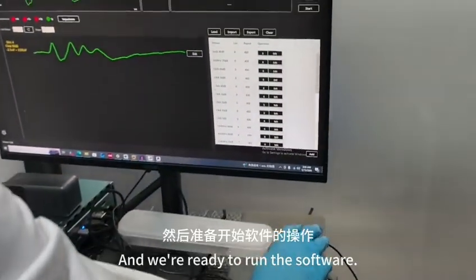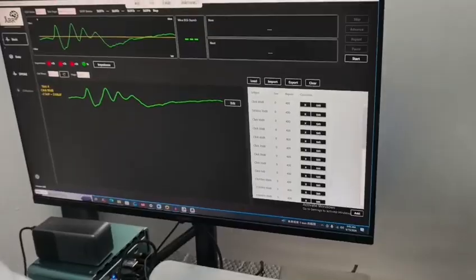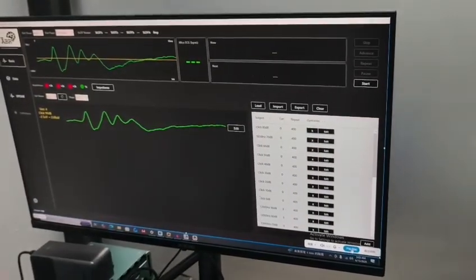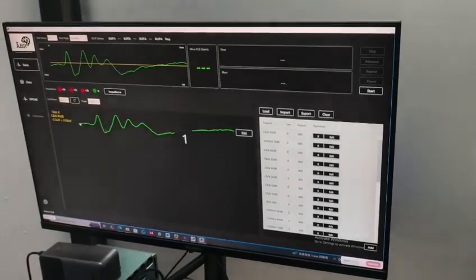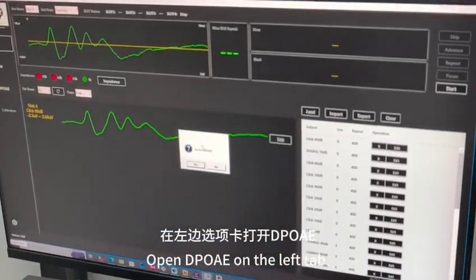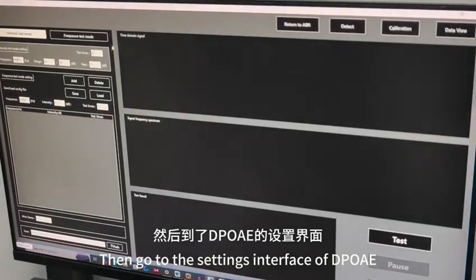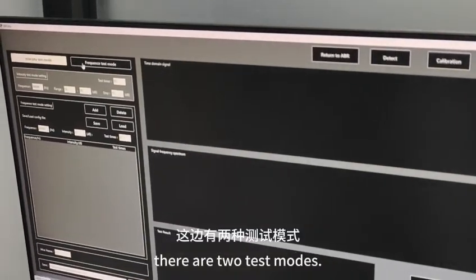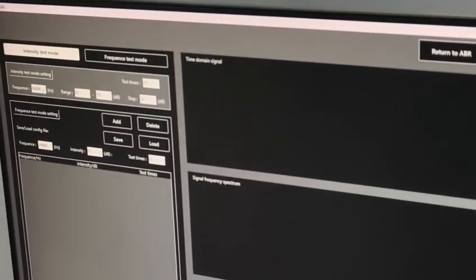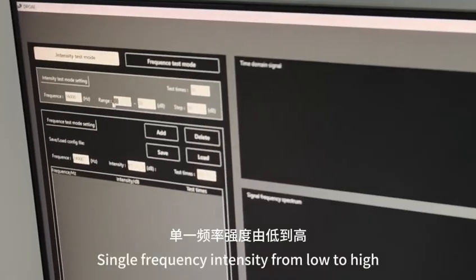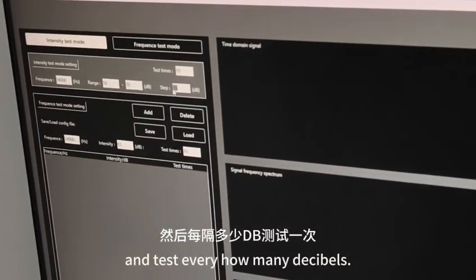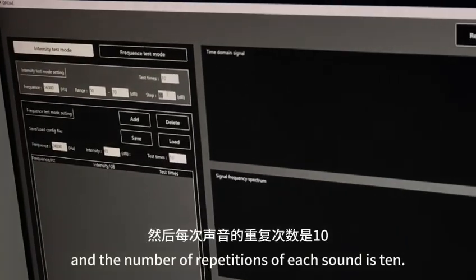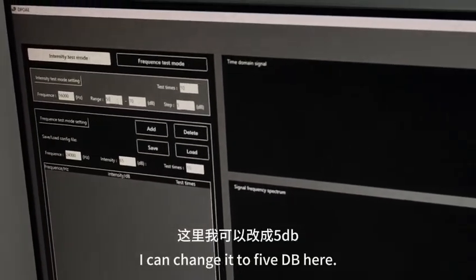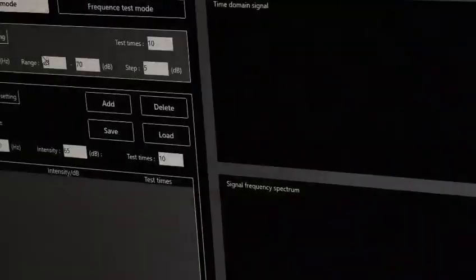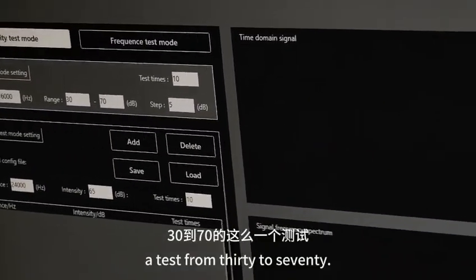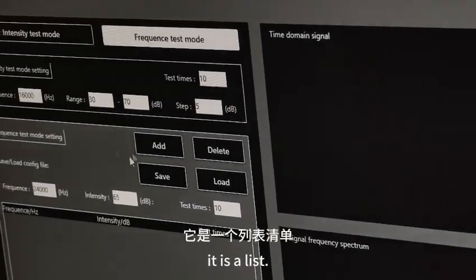And here, on the left tab, open DPOAE. Then we get to the DPOAE test interface. On the test interface, there are two test modes. The first one is a single frequency, intensity from low to high, testing every so many decibels, and the number of sound repetitions is 10. Here we can change it to 5 dB, and then 30 to 70 decibels. And the second mode is a list of options.